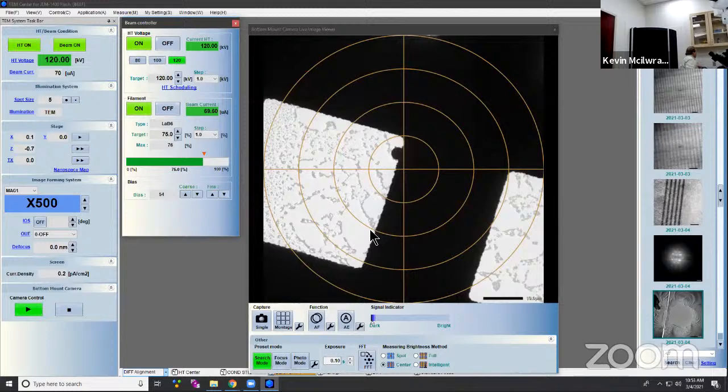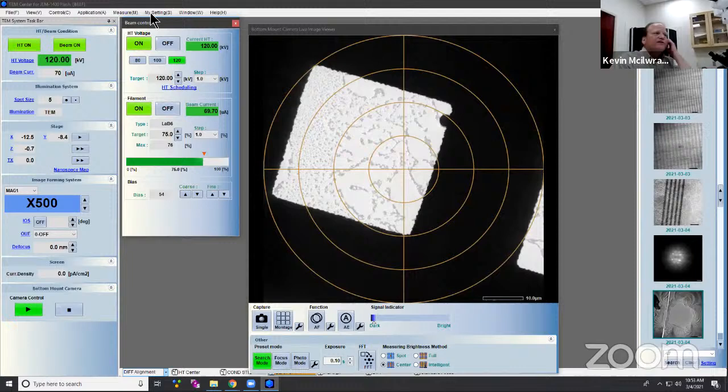But then you think, a lot of these holders are kind of thin. You get it at 4 or 8 sample in a bulky holder, you just have more issues probably with vibration and drift from a holder like that.